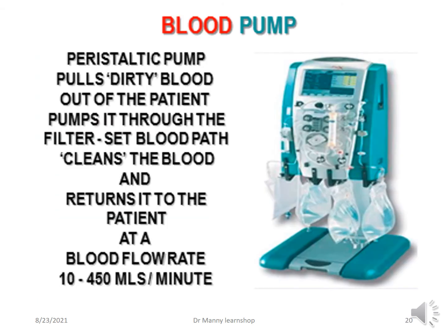Now when it comes to the blood pump, this is a peristaltic pump. It pulls dirty blood, and I'll use the term loosely. It's blood that you want to remove certain products from, whether it's urea, creatinine, potassium, toxic products, and so on. It pulls dirty blood out of the patient, pumps it through the filter set blood path, and therefore cleans the blood, and then returns it to the patient at a blood flow rate from 10 mils to 450 mils per minute.